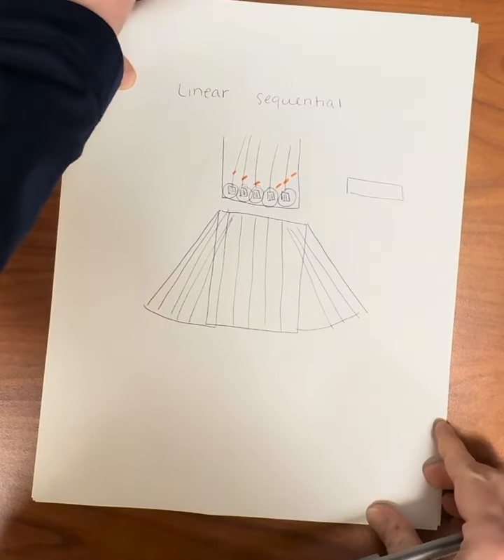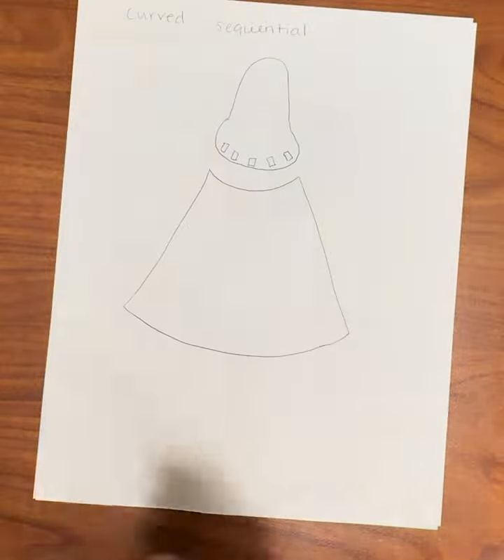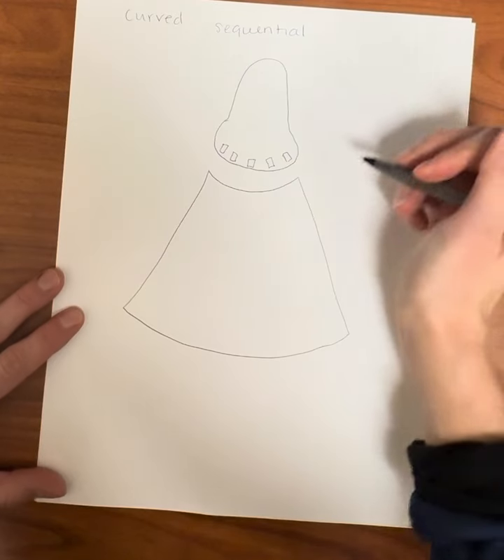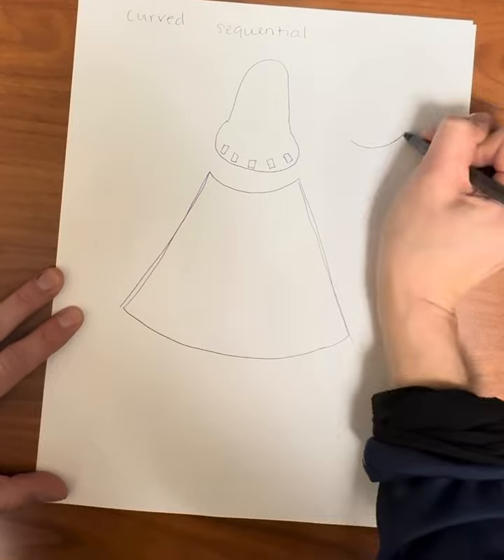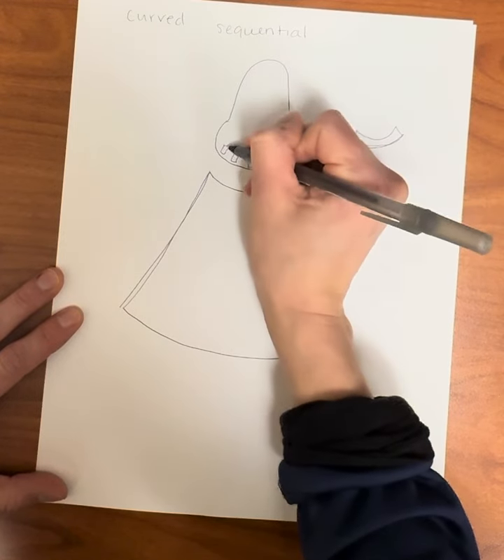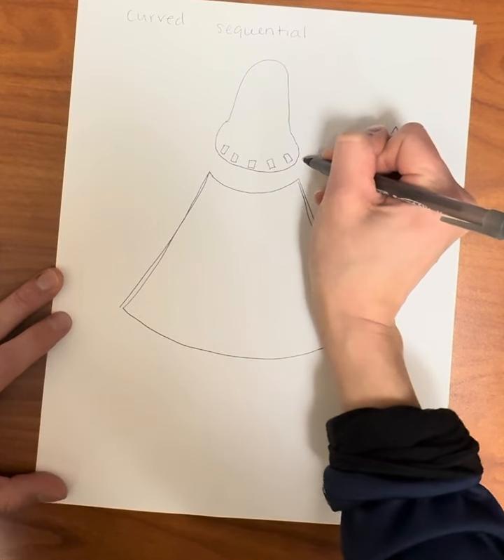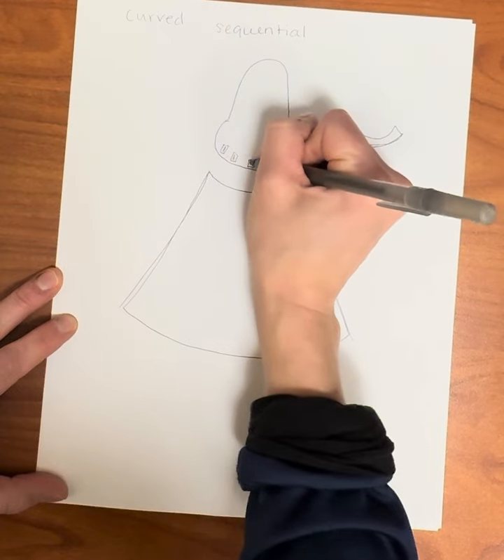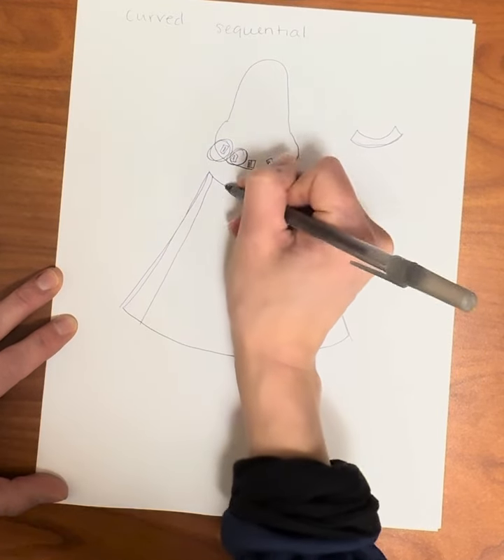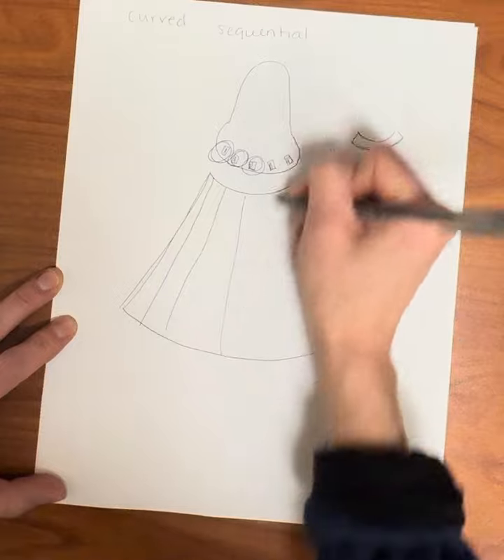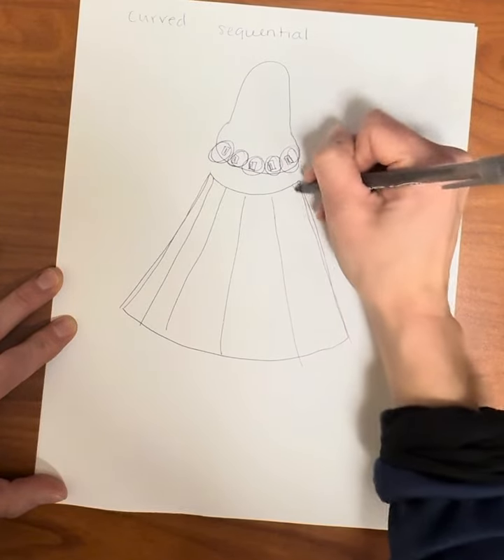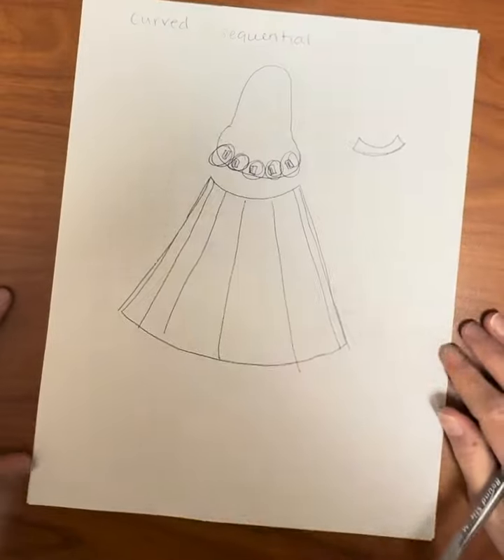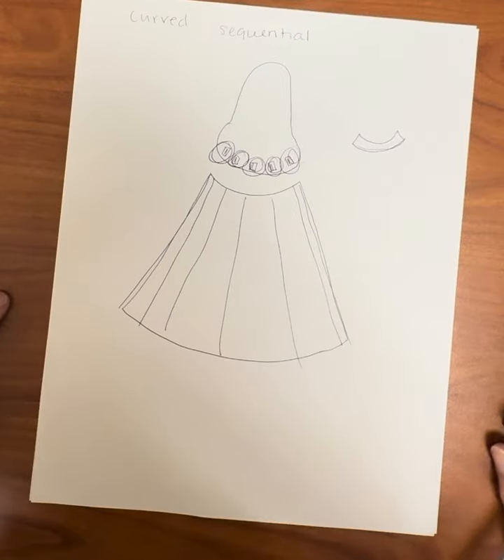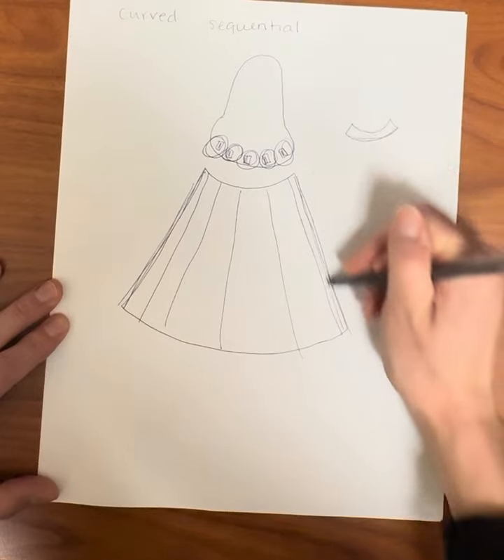Your curved sequenced array isn't usually going to be able to steer, although some modern ones might be able to. It gets this side information because of its physical shape. It has that convex footprint, which means that its elements are kind of already in a curved pattern. So this goes in sequence where each one of these elements is actually a subgroup, and it's going to go this one first to get this scan line, this one here to get that scan line, then here, middle, here, there, here, there. Because it's physically already shaped that way, it can send scan lines straight out without steering in order to get the information on our edges.